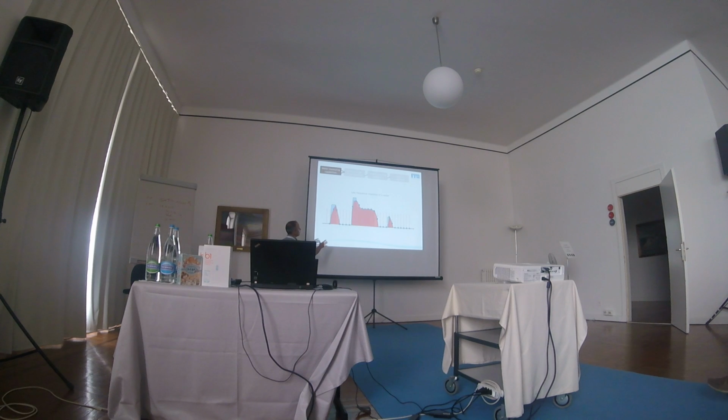In terms of volume, the volume in the red area will be exactly the same as the volume in the blue area. But in terms of trying to do shape recognition, we will have trouble. That's why, at the end, what I always recommend is to use mechanical meters, and among mechanical meters, you always use positive displacement meters.